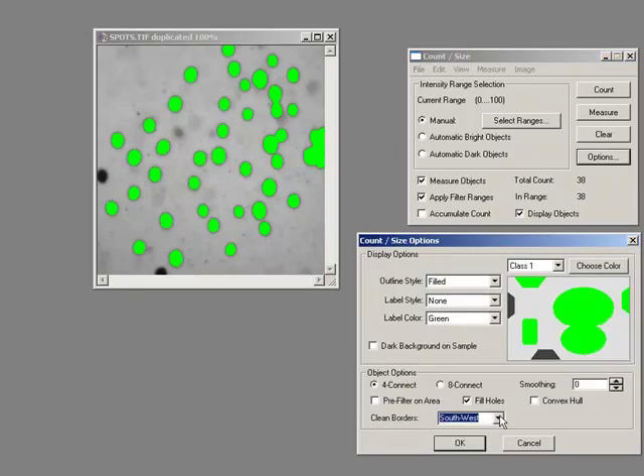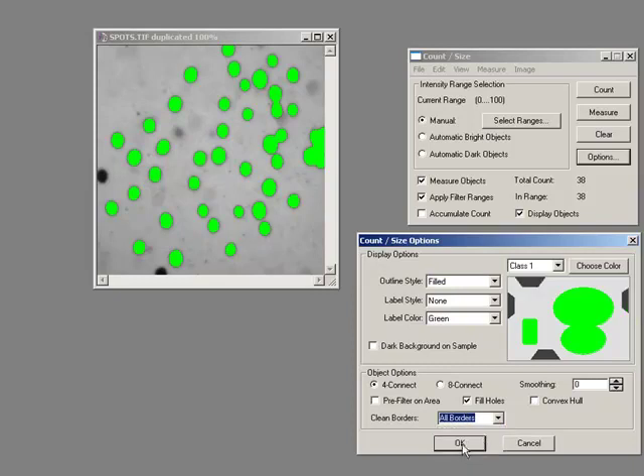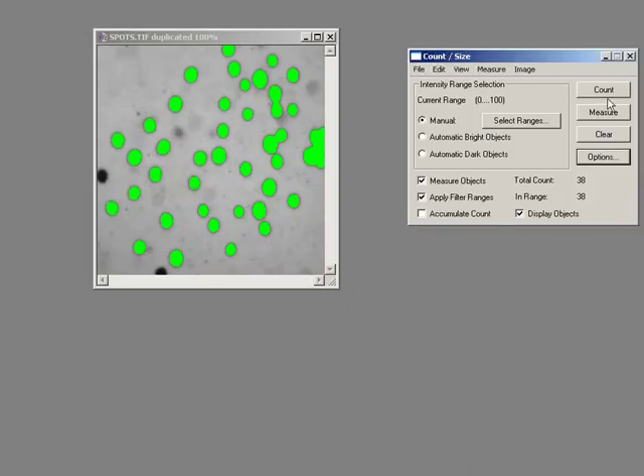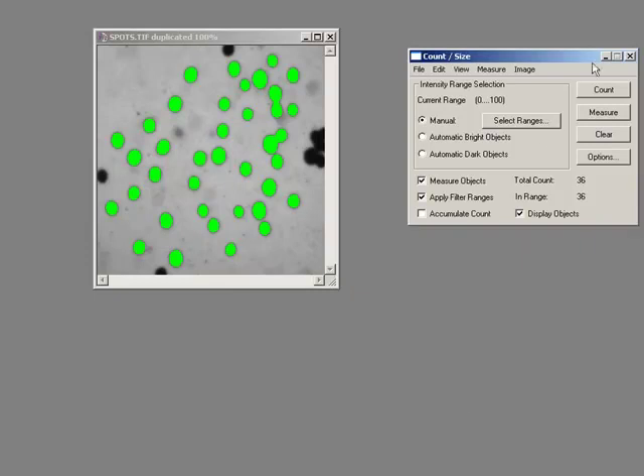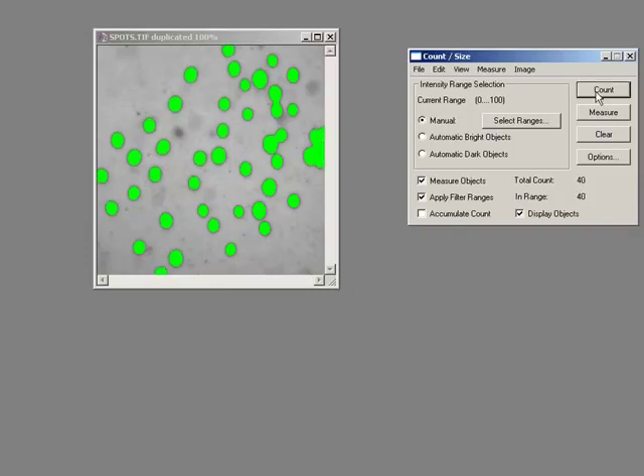Alternatively, if I was doing a particle distribution or a size distribution, I would always measure no borders because I don't know how big this object is. So for my work, I tend to always not worry about my borders. If I'm doing a proper particle count and trying to do a distribution on a slide, then I probably would look at doing all borders.